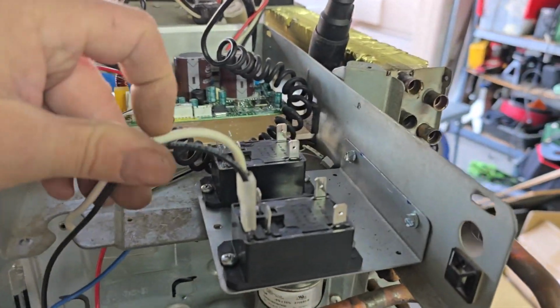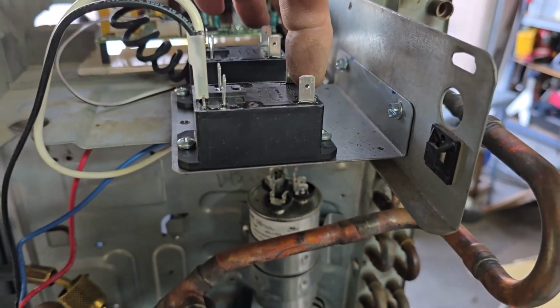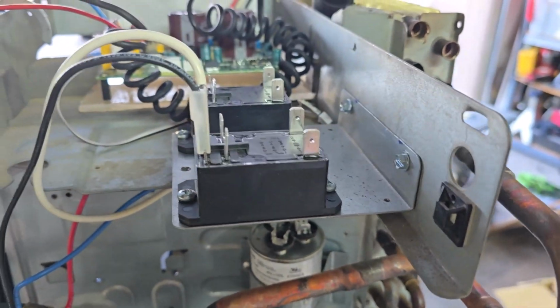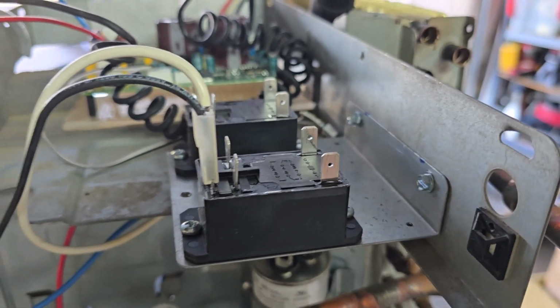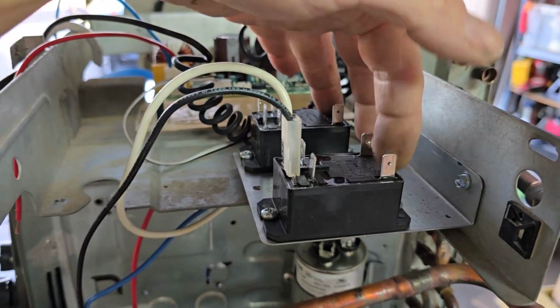So I went ahead and also slapped some relays in here. This one, and these will be 24-volt control, just having a transformer from the thermostat inside send 24 volts out to these two at the same time.